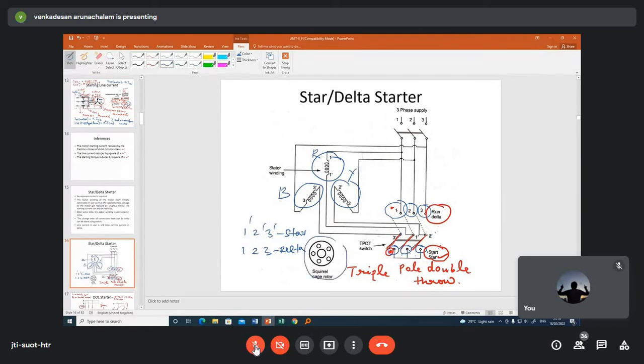Of course, this is the squirrel cage rotor. And this switch is called triple pole double throw, because it has 3 poles for 3 phases. This is pole 1, pole 2, pole 3. So the switch has triple pole, double throw. You can throw to this side or to that side. In short, it is called a TPDT switch. I think this switch is available in our lab. I have to check. If you come, you can see this TPDT switch. And this is a mechanical switch. Using this also, you can have the changeover from star to delta. But nowadays, electronics have come up, and you can use electronic methods also to change the switch from one position to another.